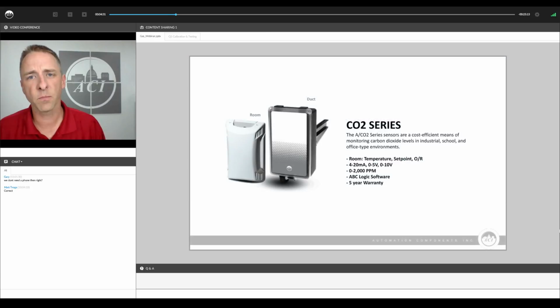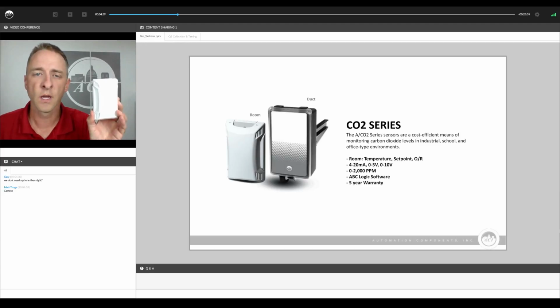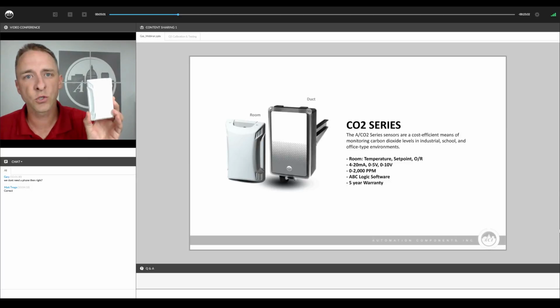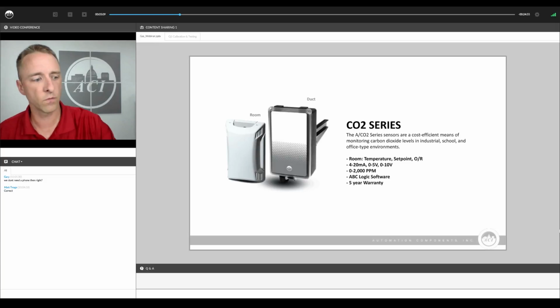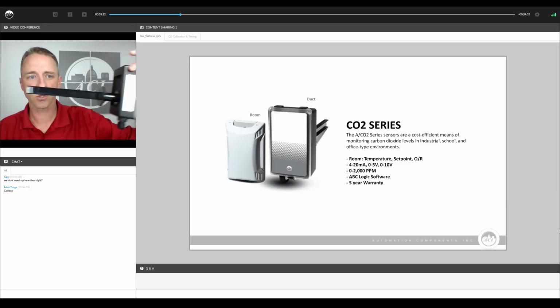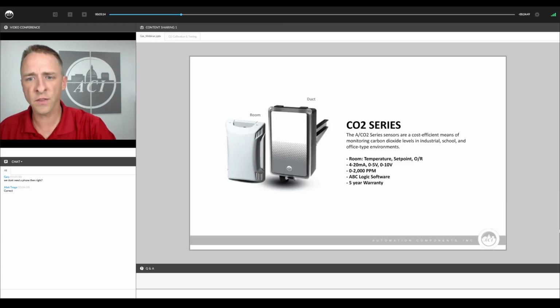We're going to start today by talking about our CO2 sensors. We have a new small compact CO2 sensor in our Aries or our R2 enclosure for wall mount CO2. It's preset to a 0 to 2,000 parts per million range, and it's also available in a duct mount configuration, which would look like this. These CO2 sensors feature a full 5-year warranty and a self-calibrating software that eliminates the need for routine maintenance and routine calibration after they've been installed in the field.